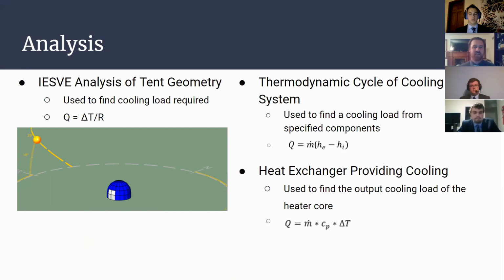Last semester for the analysis, we did the IESVE analysis of the tent geometry, which is an engineering software used by McClure engineering firm out of St. Louis that does HVAC for buildings. We used it to find the cooling load required. The governing equation for this is Q equals the change in temperature over the thermal resistance. Next, we looked at the thermodynamic cycle of cooling inside the system, and we used this to find a cooling load for specified components. The governing equation is Q equals mass flow rate times the change in enthalpy. And lastly, we analyzed the heat exchanger providing cooling. This was used to find the output cooling load of the heater core, and the governing equation was Q equals mass flow rate times specific heat times delta T.